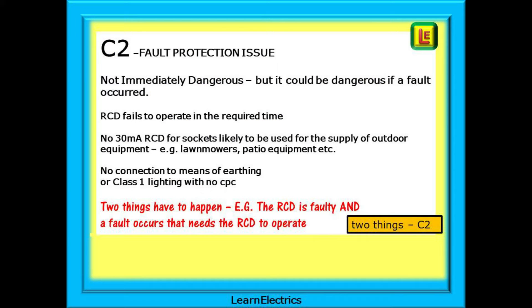C2 codes generally relate to fault protection issues. If a fault occurs, things are either not in place or not working as they should be in order to eliminate the fault before it can cause an electric shock. We say it is not immediately dangerous, but it could be dangerous if a fault occurred. Such as an RCD that fails to operate in the required time, no 30mA RCD for socket outlets likely to be used for the supply of outdoor equipment, perhaps no connection to the means of earthing, or class 1 lighting with no CPC. Think of two things that need to happen to receive an electric shock — first the RCD is faulty, it doesn't work, and then second an earth fault occurs that needs the RCD to operate, and of course it doesn't. Two things: C2.